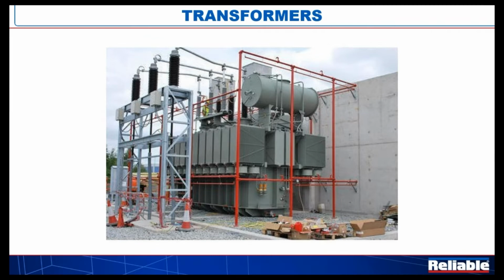Now, these transformers can be 90+% efficient, but there's always a need to remove some of that heat, and it's done very much the same way, again, as the antifreeze in your car. We have a large tank of oil. You can see it sitting up there on top. Around about the midpoint up are a bunch of radiators and fans that are drawing air, running it through a system, again, just like your car, to keep that transformer cool. And once again, you can see the piping arrangement, often painted red in a lot of these cases to identify it, but again, working its way around. And we're going to talk about further on in the presentation some of the requirements for these various types of protection schemes.